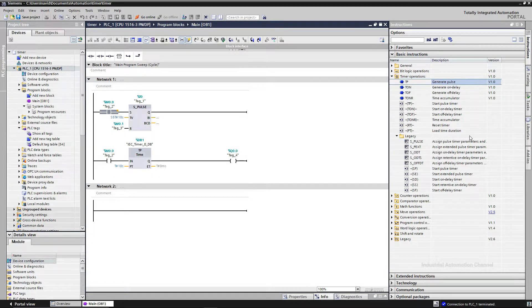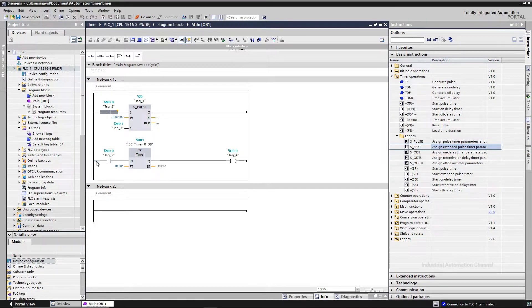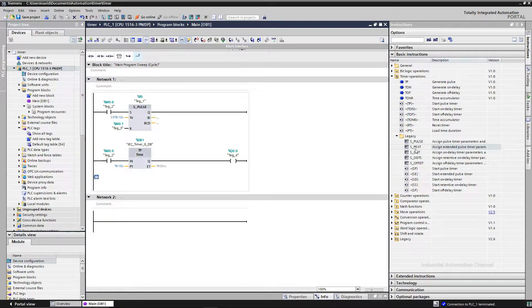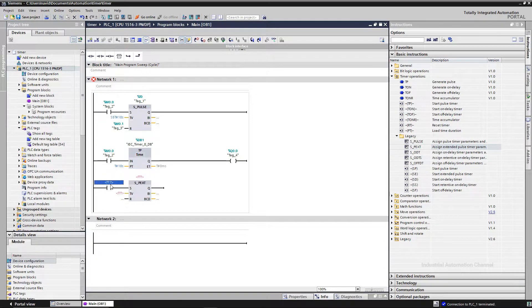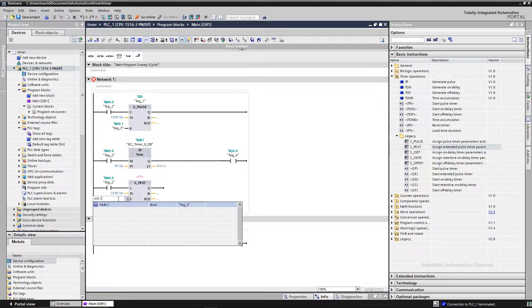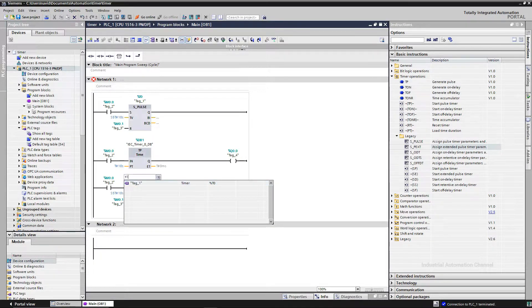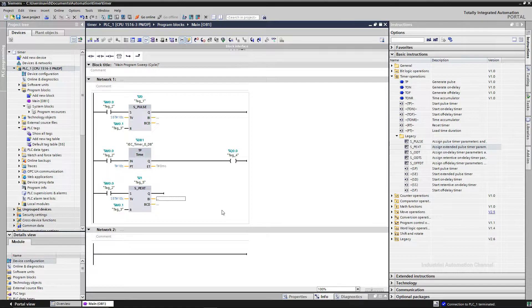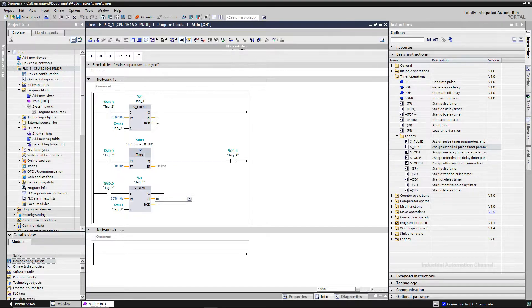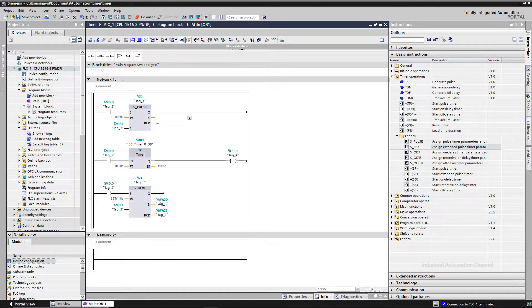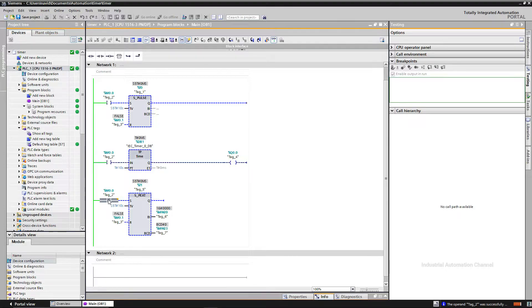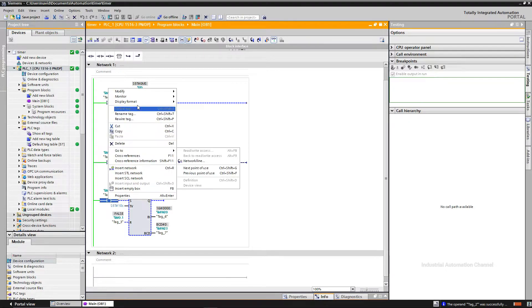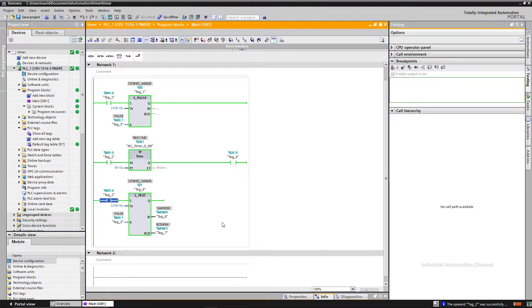The next timer is an extended pulse timer. All the inputs and outputs are like S_PULSE timer. Let's simulate it. I give a memory word to see the BI and BCD outputs. Whenever I turn on the start input, the output will be on. After 10 seconds, the output is off.